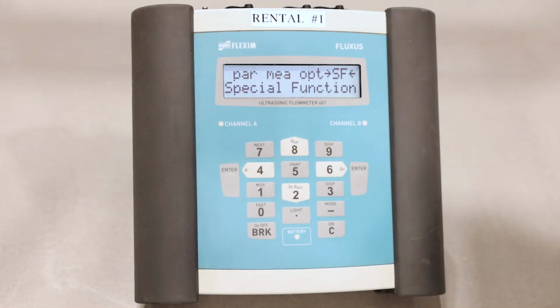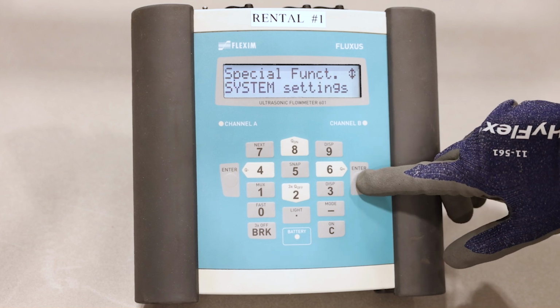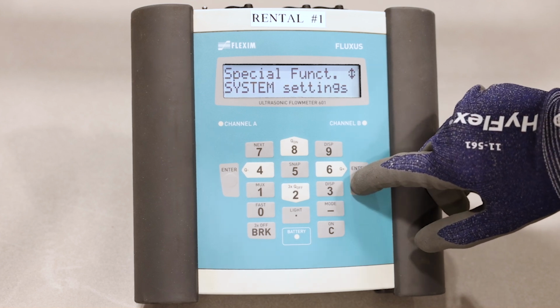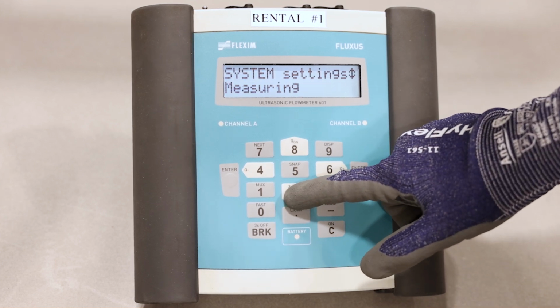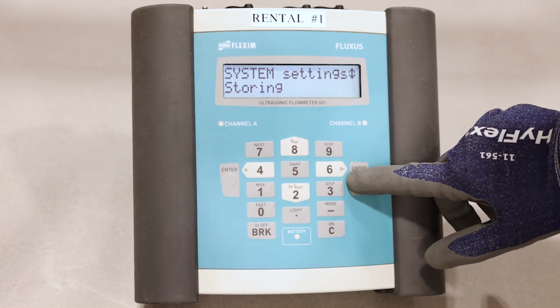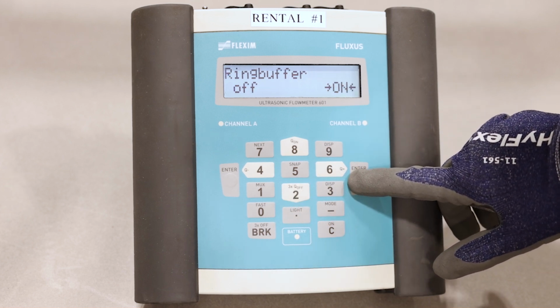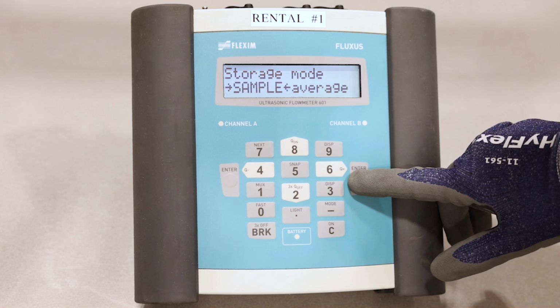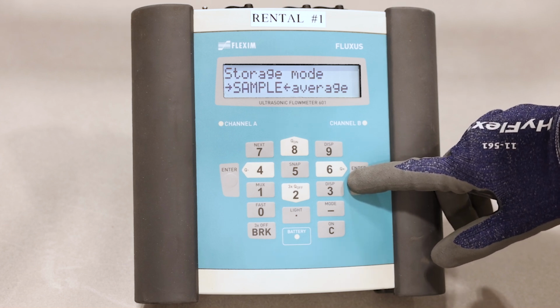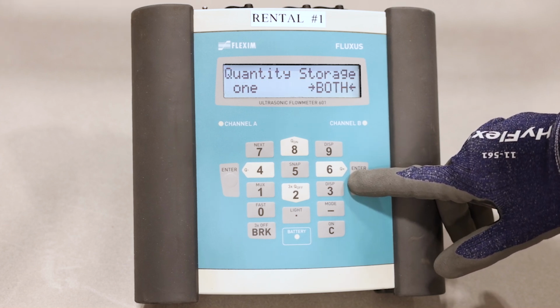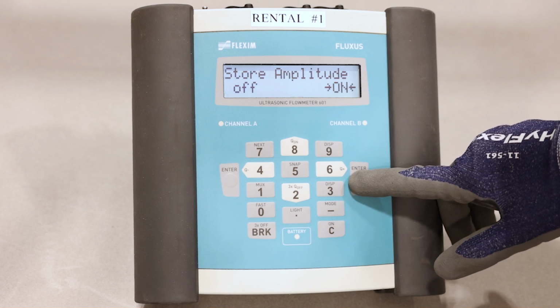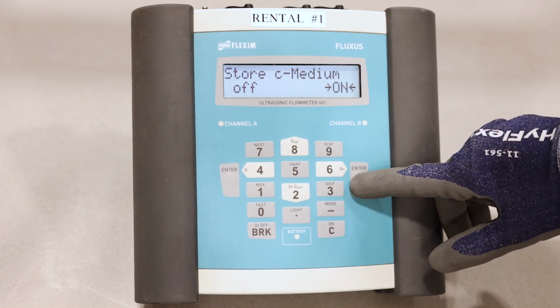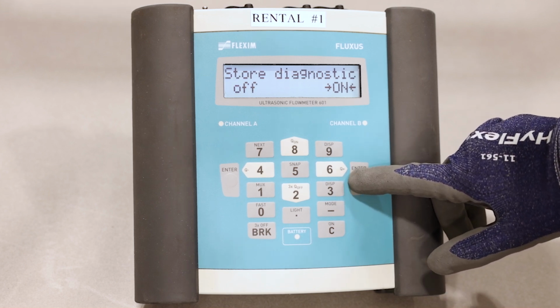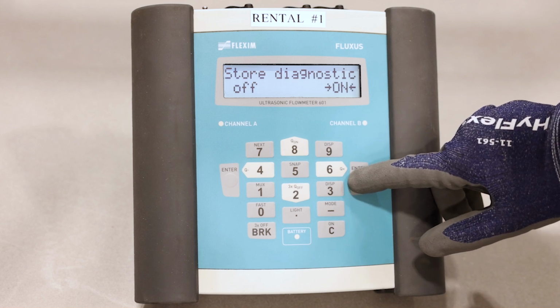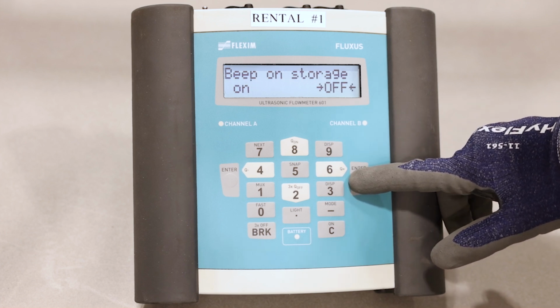The data logger is what we will set up next. Enter the Special Functions menu, System Settings, Storing. Turn ring buffer on, sample mode to sample, quantity storage to both, store amplitude to on, store C medium to on, store diagnostics to on, and beep on storage to off.